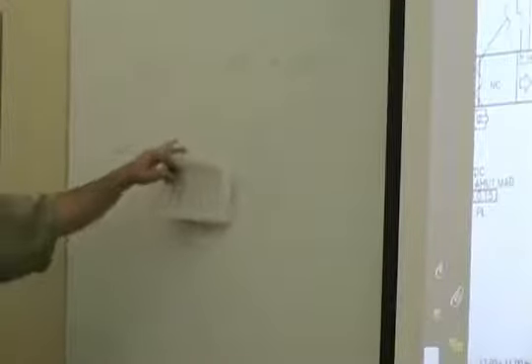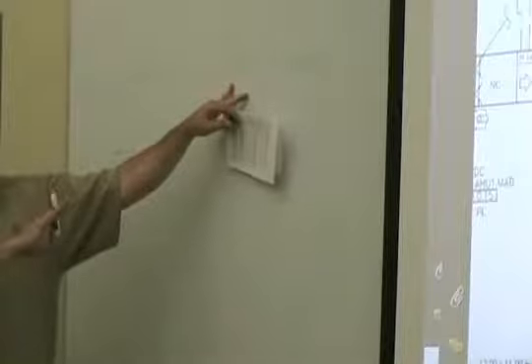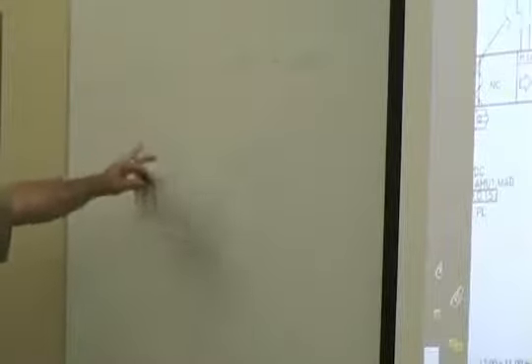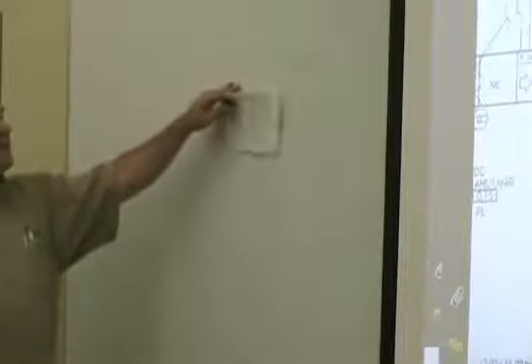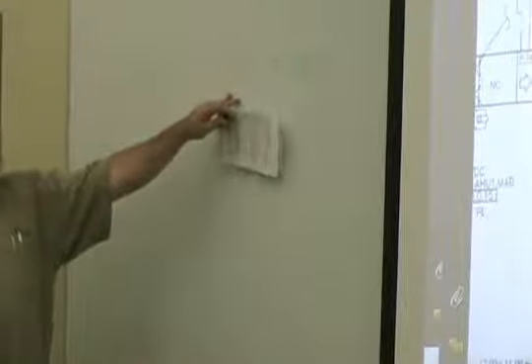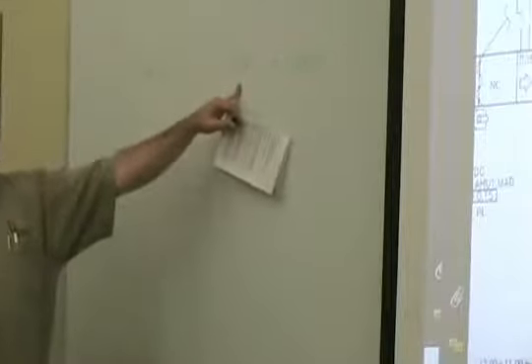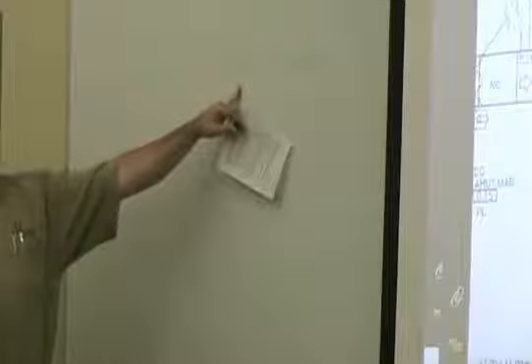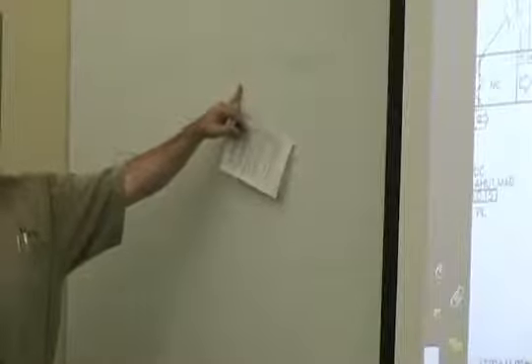5 people need a certain number of CFM for fresh air. I'm guessing here, I don't know these numbers. Steve will know these numbers off the top of his head. But let's say that whatever it is, 5 times that amount comes up to this 100 CFM, just for calculation purposes. So I need 100 CFM in this one room, out of hundreds that this air handler may be serving. I need 100 CFM of fresh air in this space. So if I'm down at 100 CFM, what percentage of outside air do I need in that space? 100%. So what fraction of outside air do I need in my air handler?